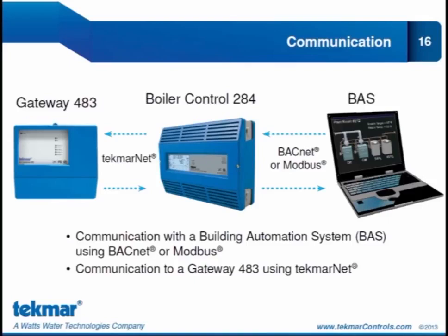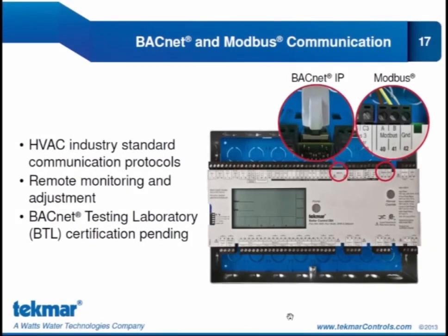Just a note here though, the gateway allows adjustment of thermostats only, whereas communication from a building automation system using BACnet or Modbus provides greater adjustment capability. Let's talk a bit more about the BACnet and the Modbus communication. They are both HVAC industry standard communication protocols. I've been asked before, can we do both? Can we have BACnet and Modbus at the same time? No, you cannot. It is one or the other.